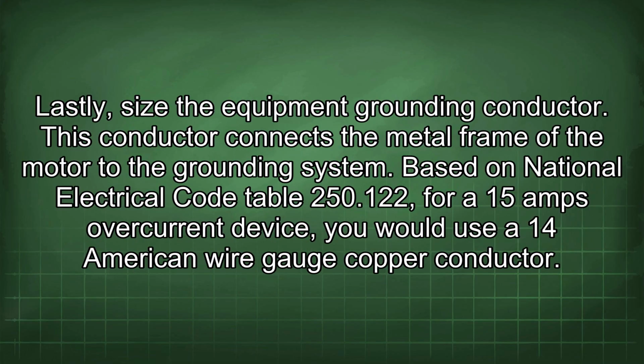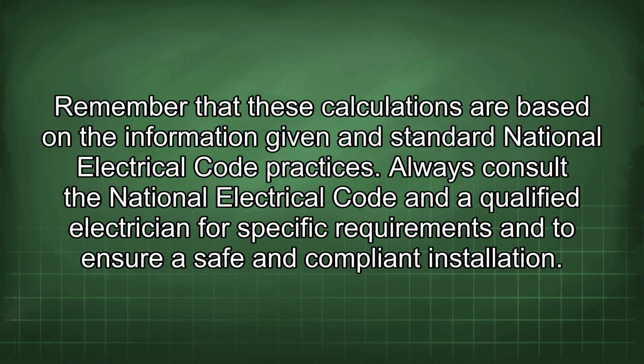Lastly, size the equipment grounding conductor. This conductor connects the metal frame of the motor to the grounding system. Based on National Electrical Code Table 250.122, for a 15 amp overcurrent device, you would use a 14 American wire gauge copper conductor. Remember that these calculations are based on the information given and standard National Electrical Code practices. Always consult the National Electrical Code and a qualified electrician for specific requirements and to ensure safe and compliant installation.